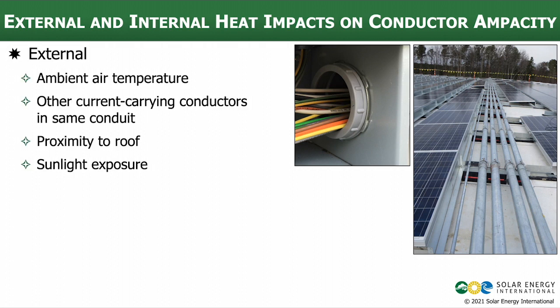External sources include things like the ambient air temperature. Conductors are rated at a certain temperature, and if they are in an environment that's different than that, we're going to have to adjust their ampacity accordingly. Another form of external heat would be other current-carrying conductors in the same conduit. When a conductor carries current it's going to give off heat, and the more conductors we have in a conduit, the less air there is to dissipate that heat.